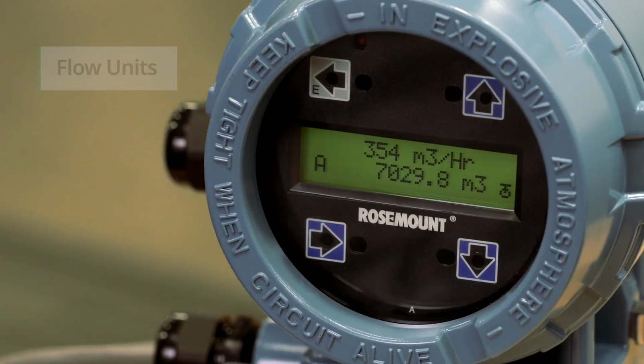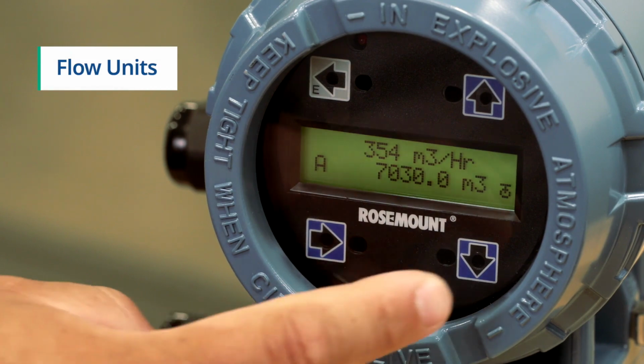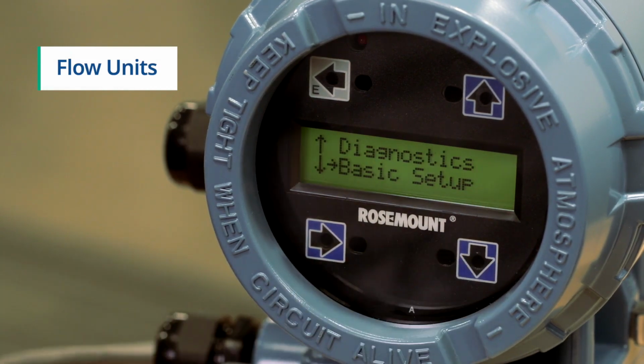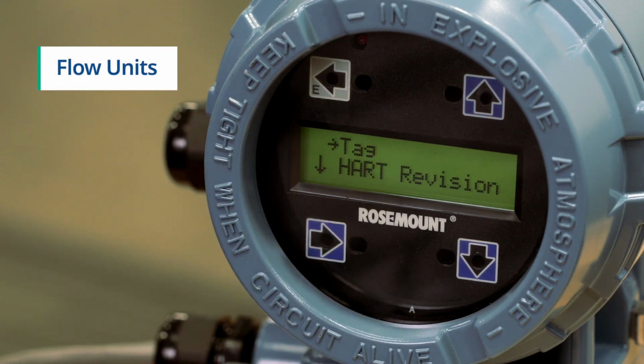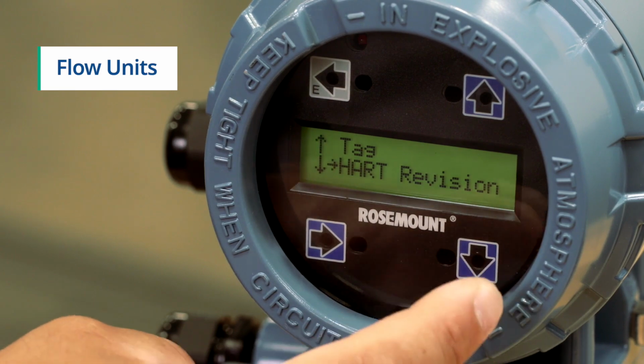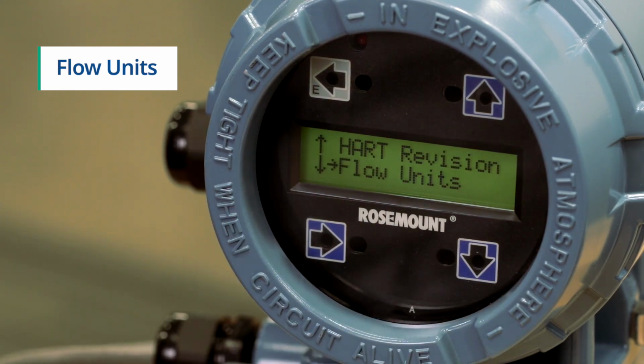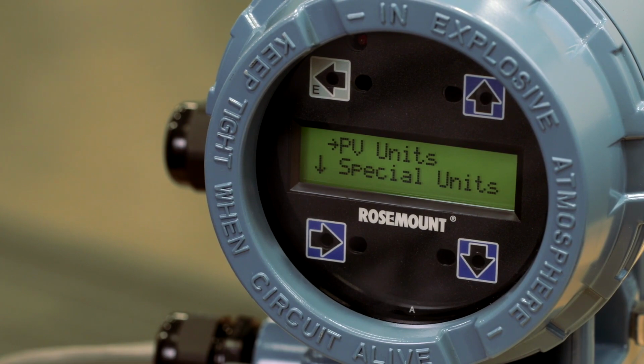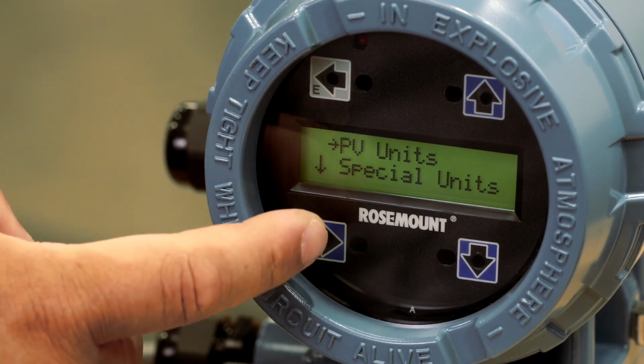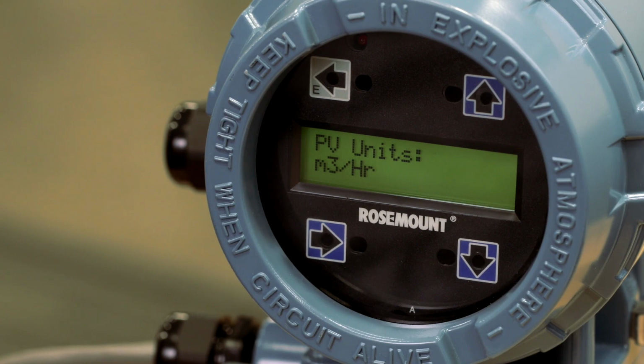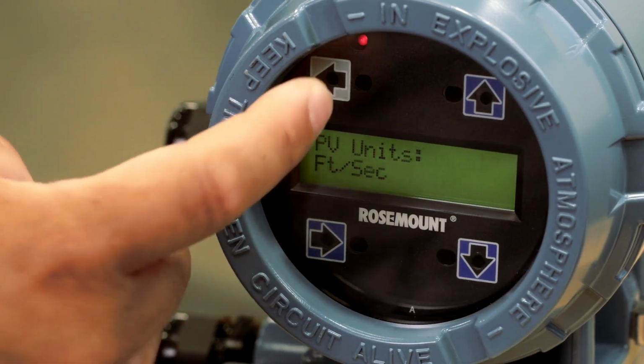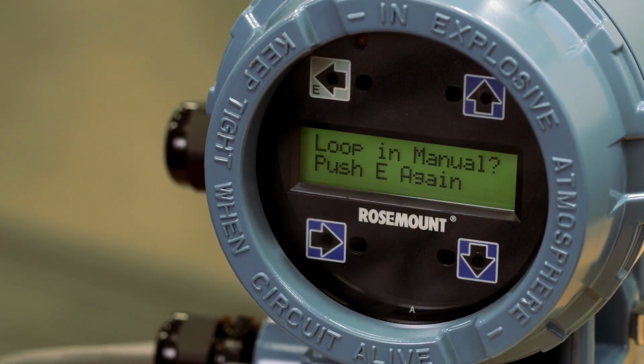To configure the flow units from the home flow rate screen, press the down arrow three times to access the basic setup menu. Then press the right arrow to select the basic setup menu. Press the down arrow until flow units is highlighted, and then press the right arrow to select flow units. Press the right arrow to select PV units. Press the up and down arrows to scroll through the options for flow units, and press the E button to select the flow units. Finally, press the E button again to save your selection.